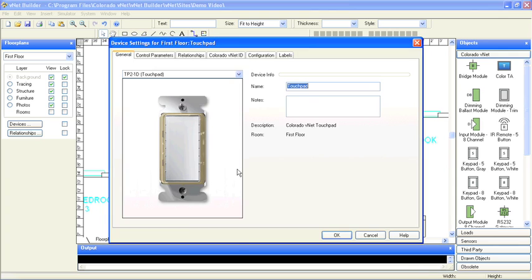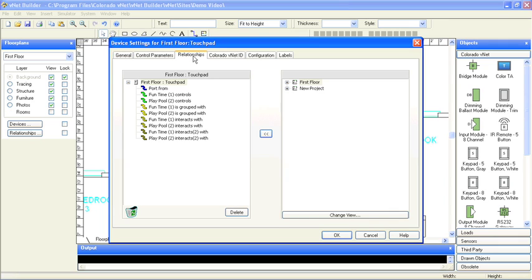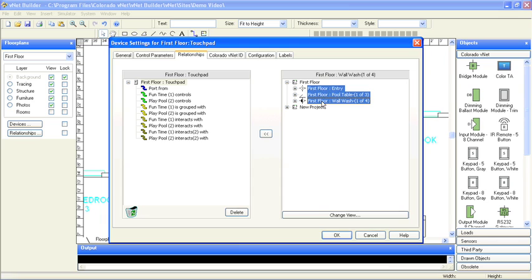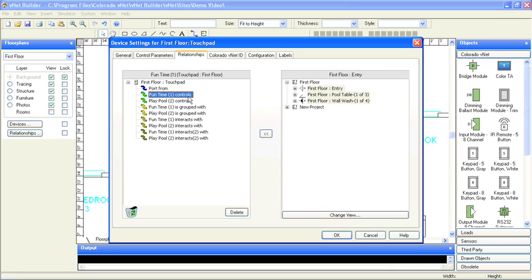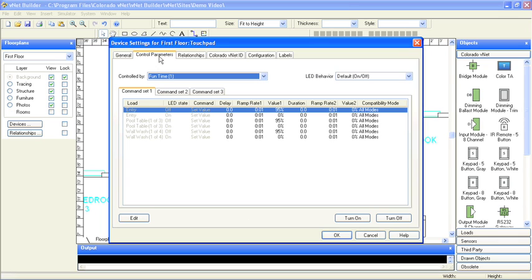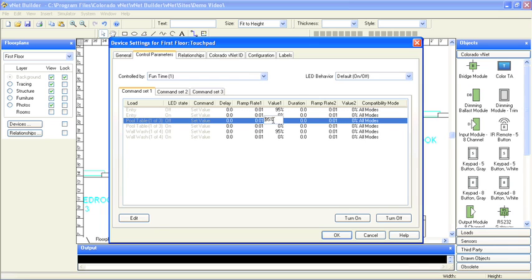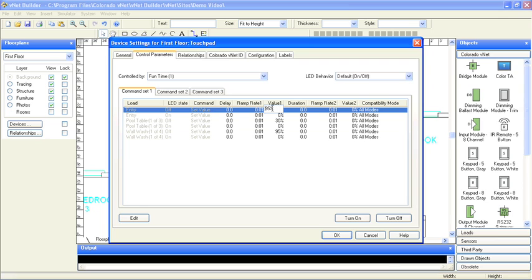I'll use the Relationships tab to define which loads are in these scenes. I'll simply drag and drop the loads onto the button legends to make the connections. To complete the scenes, I'll use the Control Parameters tab. There's a lot of information here about how the loads will respond as part of this scene. By default, they will brighten up over a second to 95%. For the fun time scene, I'll have the pool table pendants go to 30% and set the entry can at 50%.